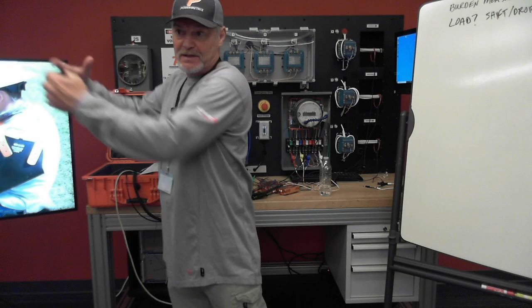So that's what he's doing now - troubleshooting 101. He's testing the different items in the link, the connection between the test kit and all the way up to where the flexes and connections are at the meter installation and test switch, right? So you're following it all back to make sure it couldn't be one of those cables or one of those flexes. Thanks.